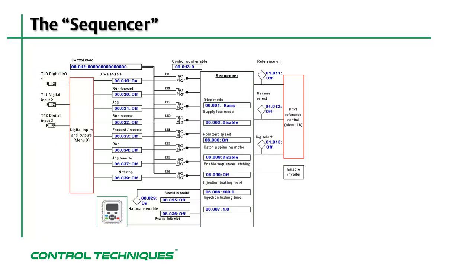Sequencer functions, or destinations, are typically assigned to the drive's digital input terminals. For example, the Unidrive M400 that I'm using today has the sequencer function run forward assigned as a destination for digital input number 3.